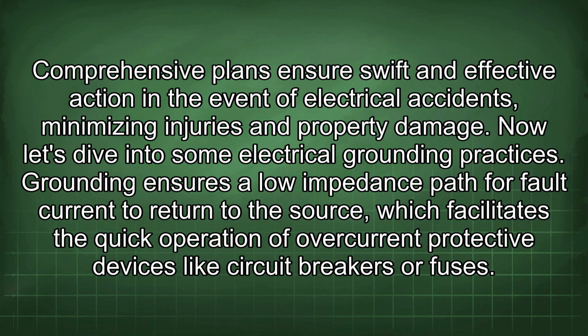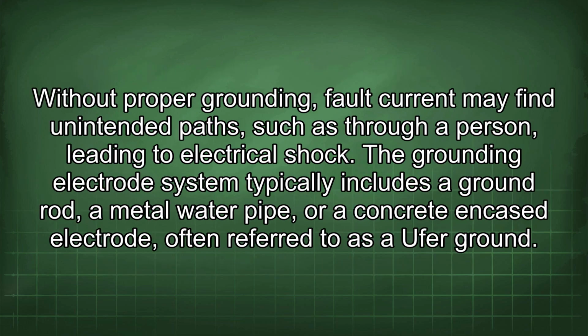Now let's dive into some electrical grounding practices. Grounding ensures a low impedance path for fault current to return to the source, which facilitates the quick operation of overcurrent protective devices like circuit breakers or fuses. Without proper grounding, fault current may find unintended paths, such as through a person, leading to electrical shock.